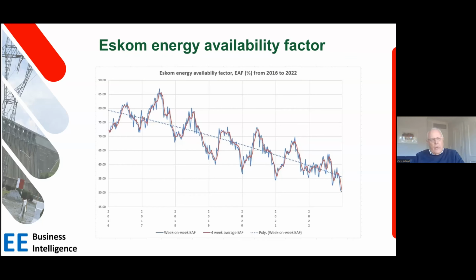It takes about 3 to 4 months of extended shutdown to do deep level maintenance on a generator, so they can't work on them all at the same time. They work on maybe a group of 3, 4, or 5 at a time, in sequence. This means you cannot have a sudden change in the availability factor, because there are 80 of them and you can't work on them all simultaneously. So what is the best one can expect?